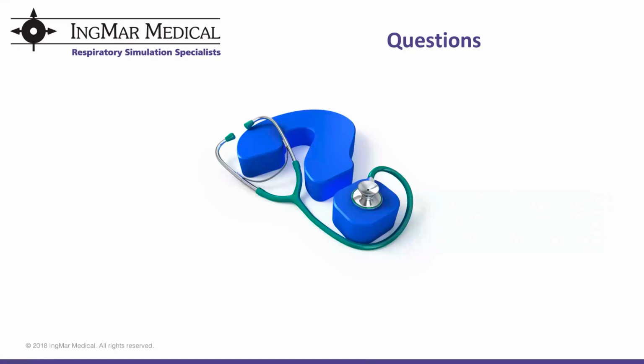It's a great question. The ASL 5000 actually does not have a flow sensor, whereas it has a pressure sensor. The reason is because flow sensors tend to experience drift, and therefore they have to be recalibrated much more often. In this case with the ASL, because we have an optical encoder which very accurately provides us with volume, we send the raw volume data to the software, which is our main ASL 5000 software, and we run a derivative calculation against that volume to determine our flow.